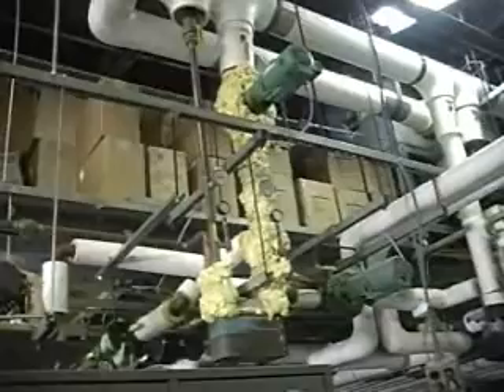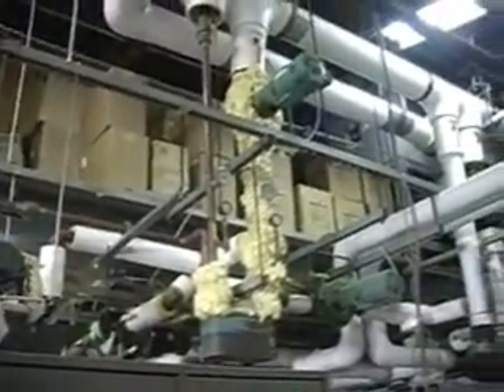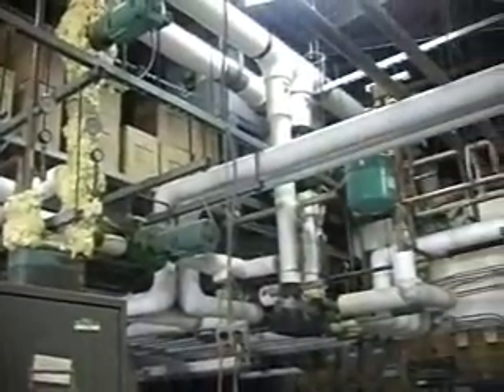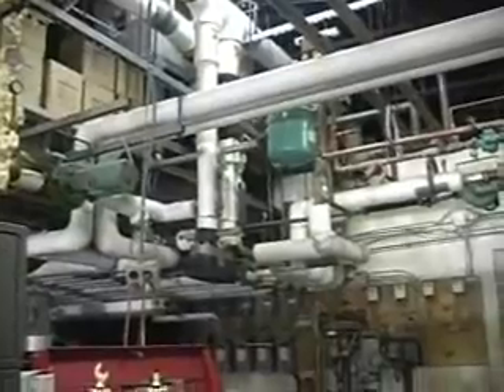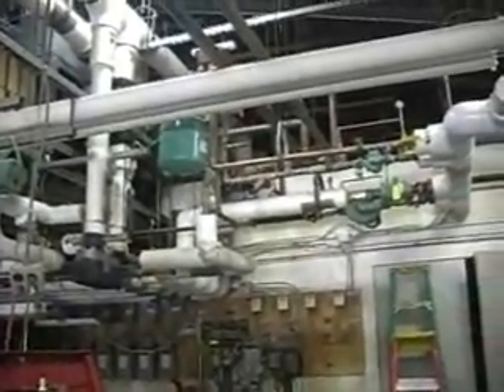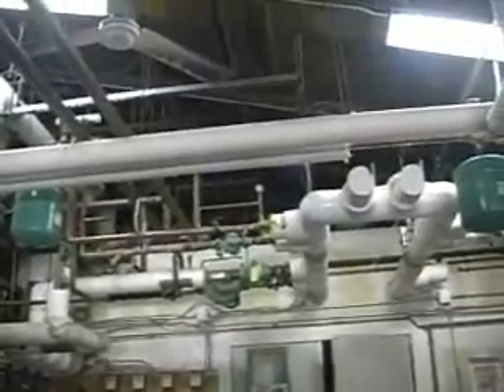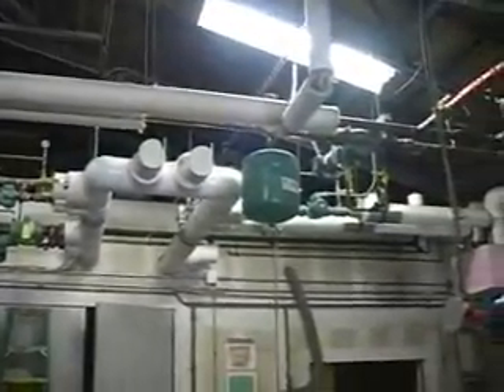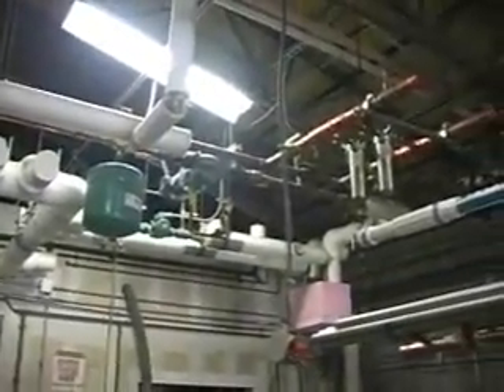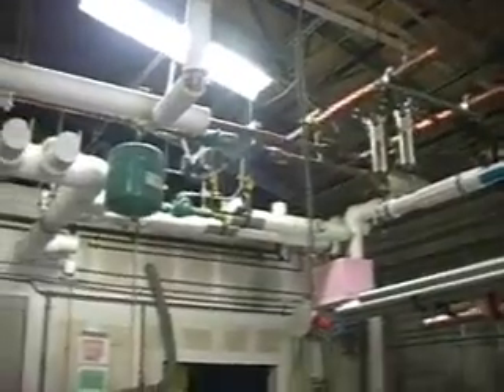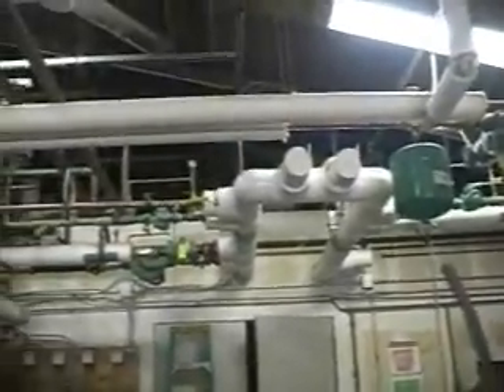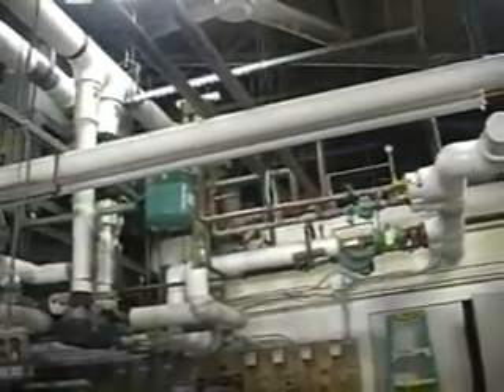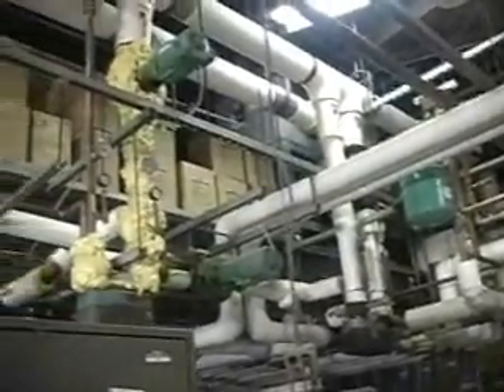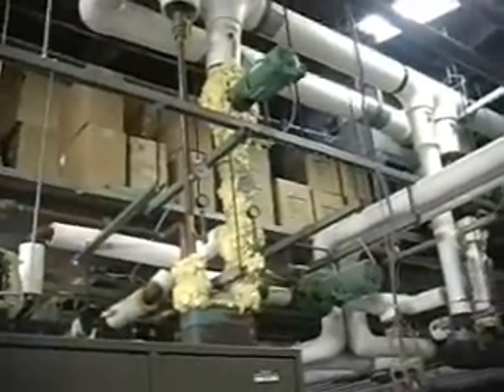At the heart of our energy efficient system is what we call our tri-generation. We have two diesel generators that click on and make electricity. We then save the heat created off those engines. In the wintertime, that heat goes through pipes and heats the building. In the summertime, the heat first visits an absorption chiller, which converts the hot into cooling to cool the building. Once the energy is used up, the water gets recycled back in, making it a closed loop system for heating and cooling the building.